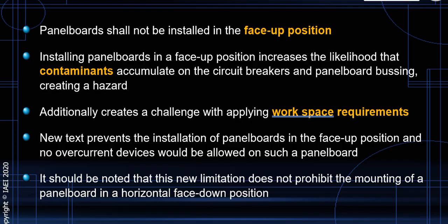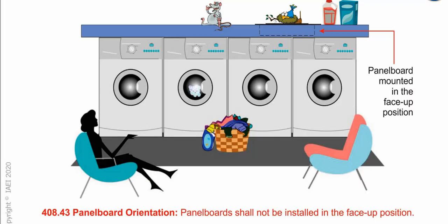Additionally, it creates a challenge with applying workspace requirements, and new text prevents the installation of panel boards in the face-up position, and no overcurrent devices would be allowed on such a panel board. So this is from the 2020 changes. And it should be noted that this new limitation does not prohibit the mounting of the panel board in the face-down position. Aha! As I said, this change is from the 2020.